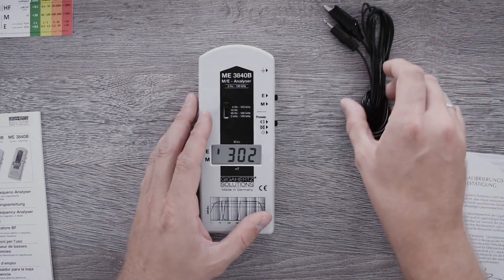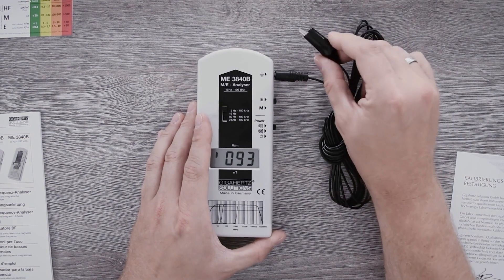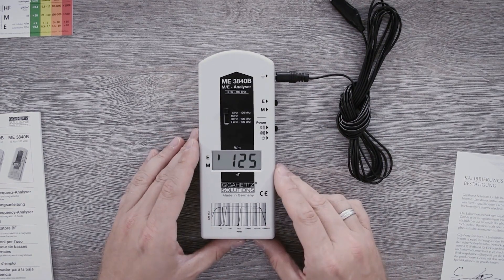The second option is a potential bound measurement. For this, you can plug the grounding cable right here into the socket. Via the crocodile clamp, connect the measuring device to a grounded point, for example the protective contact of your plugs in the wall.